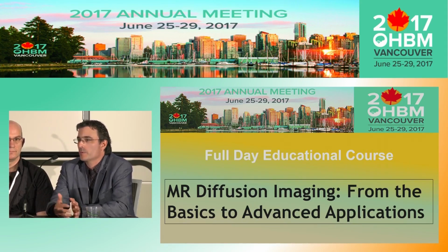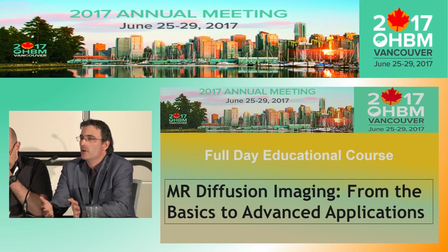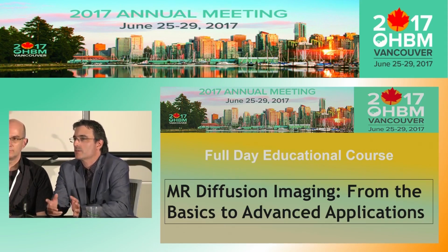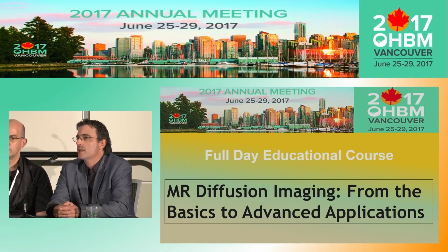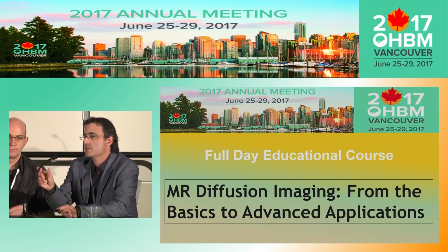Now, of course, will we be able to do a lot of the other algorithms that need higher B values and so forth? No, but I can get a lot of information out of that data set. I can get kurtosis, I can do crossing fibers, and so I think it's a good compromise. And I'm still getting higher spatial resolution, which is something I think we should take advantage of with the greater signal that we have on our new systems, especially if you're not going to extra high B values. So anyhow, that's just my personal opinion.